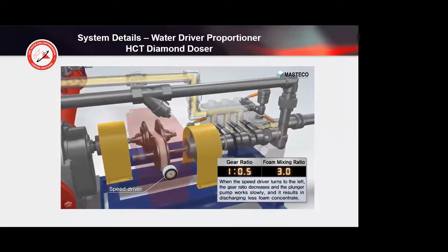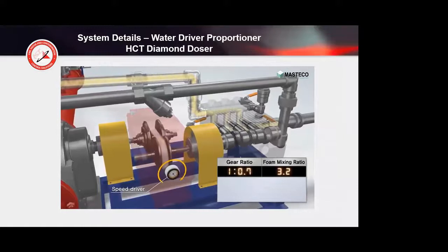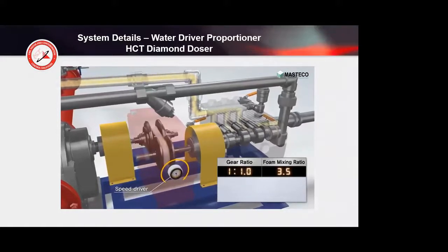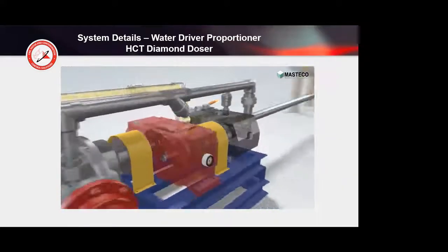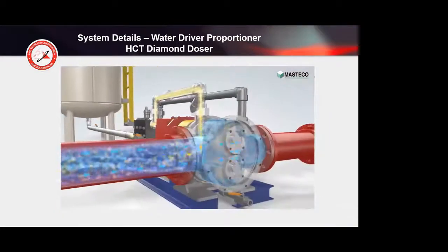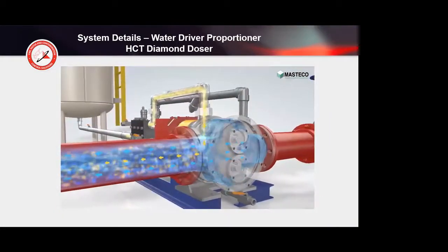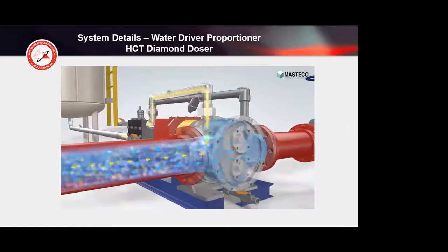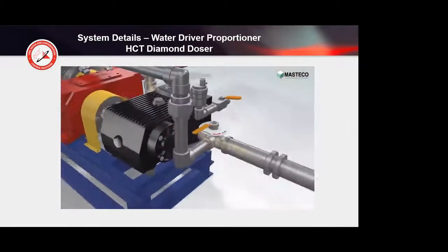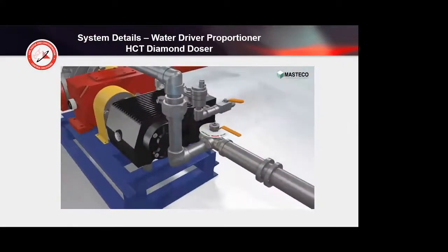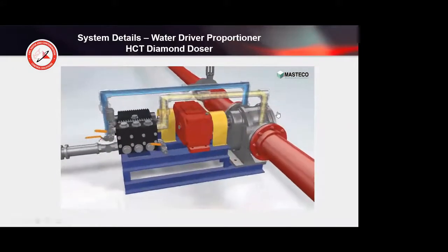With the bladder tank, you can't use those with a closed head system, because if only two heads open, then you don't have enough flow to proportion. But with the water-driven proportioner, if two heads open, you have enough water to proportion - same as if 10 heads open. That just means water's flowing faster through the water throat.